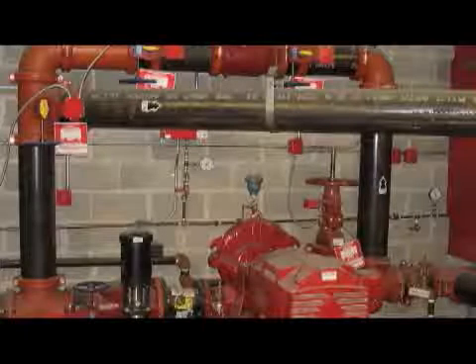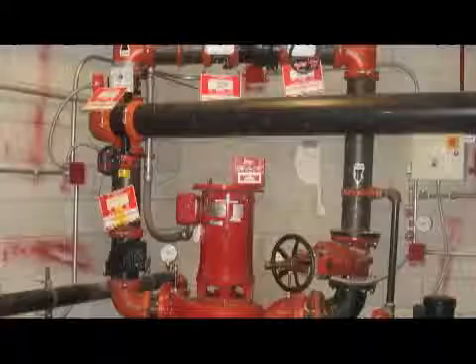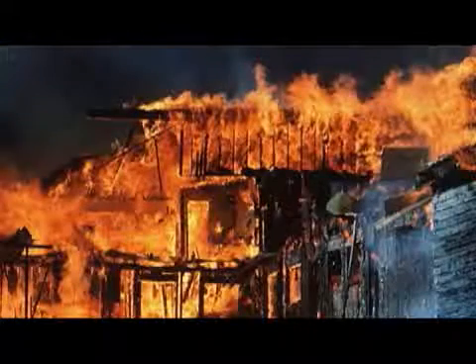So it does happen. Let's talk a little bit more about your inspection services. You mentioned that you actually install, but inspection is an important part of what you do, isn't that right? Yes, Heads Up Fire Sprinkler Service and Repair has inspections that the New York City Fire Department requires, much like elevators be inspected on a semi-annual or annual basis. The fire sprinklers have to be inspected once a month. It's a visual inspection, that you go into buildings, whether we install them or they're existing throughout the city, to make sure that the valves obviously are open, that there are no painted sprinkler heads, and you're not missing any signs for the fire department to go in and find where the sprinkler rooms are, the equipment and everything. So the city is also required to have these sprinkler systems inspected on a monthly basis, just to make sure that they're up and running and that there are no big violations pending on them. So they enforce the maintenance of it as well.